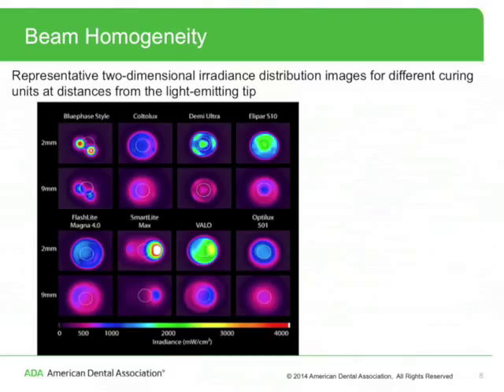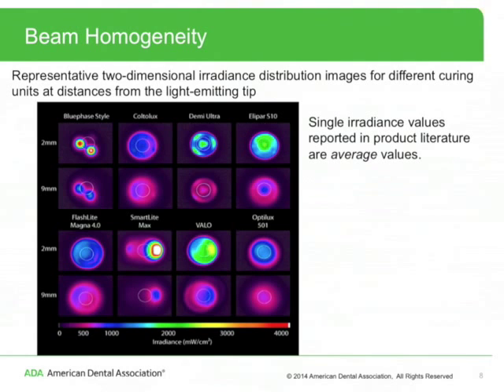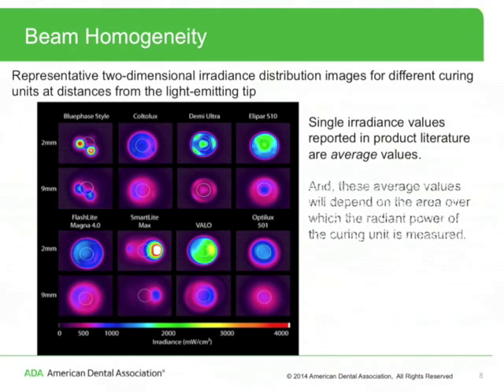It can be seen from the color-coded images that the irradiance distribution varies across the light beam for all LED curing units. For example, some profiles such as the Bluephase Style and the SmartLite Max range from below 500 milliwatts per centimeter squared to over 4,000 milliwatts per centimeter squared. Single irradiance values reported in product literature are average values, and these average values will depend on the area over which the radiant power of the curing unit is measured.